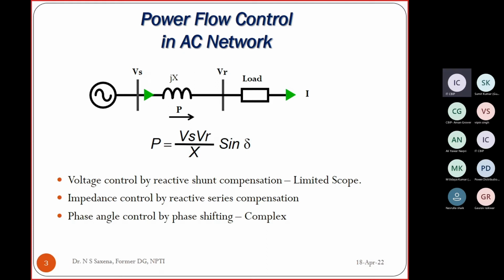1.05 is the limit, you cannot go beyond that, otherwise the voltage equipment will get overstressed. So with 1.05 and the square of that for sending and receiving end, there's very little scope, very limited scope for changing the voltage. Of course, voltage can be changed by reactive shunt compensation, which can push the voltage, but it's a very limited scope.